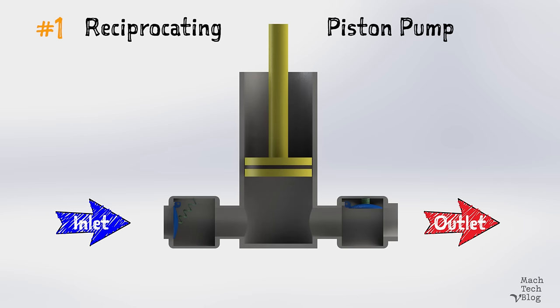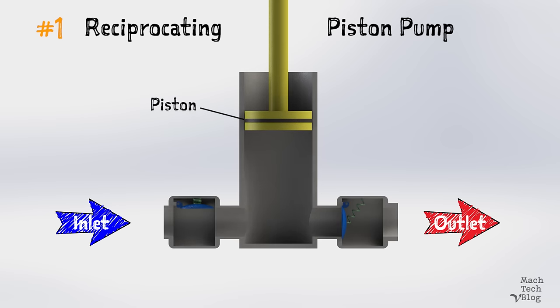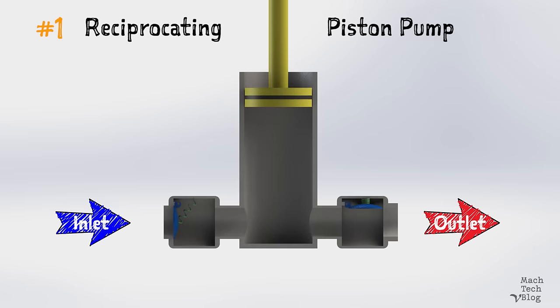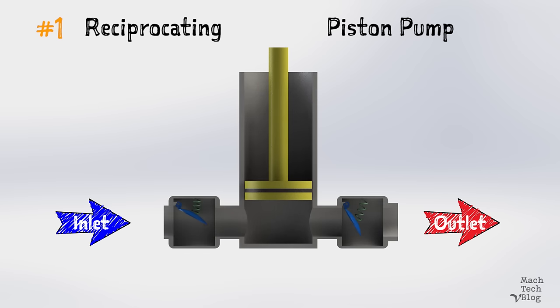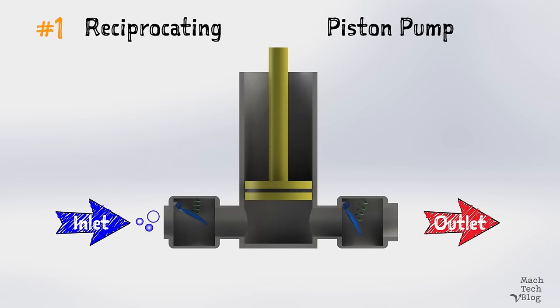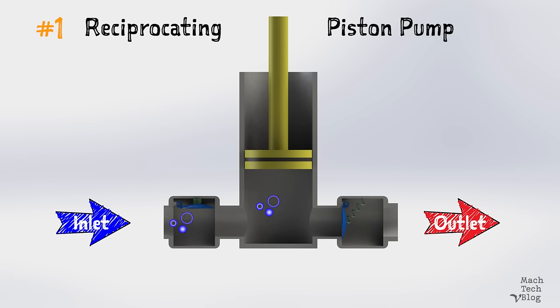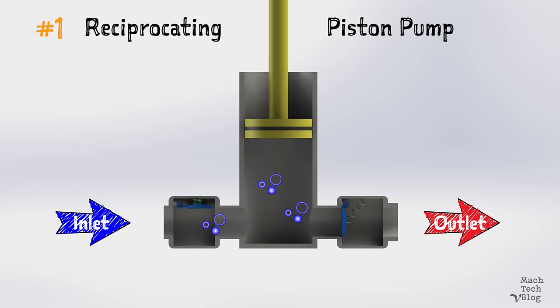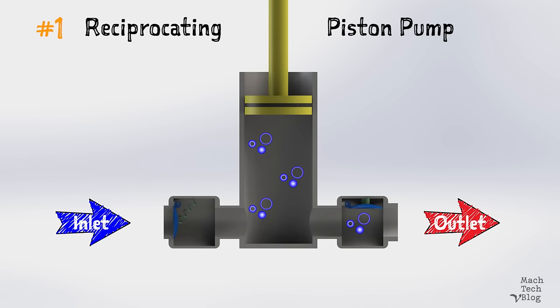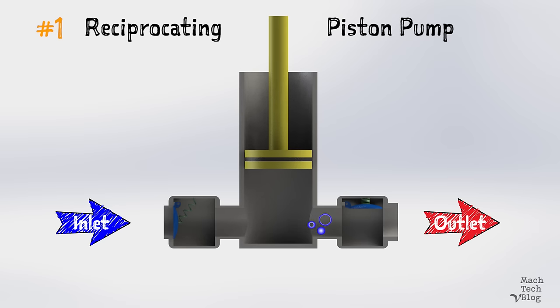The mechanism consists of a reciprocating piston inside of a cylinder with check valves at both the inlet and the outlet. When the piston is on its suction stroke, which is the upstroke in this case, the chamber inside of the cylinder expands, the pressure drops, the check valve on the suction side opens, and fluid is admitted through the inlet. By definition, check valves permit flow in one direction only, so they help to prevent backflow and direct the fluid through the pump.